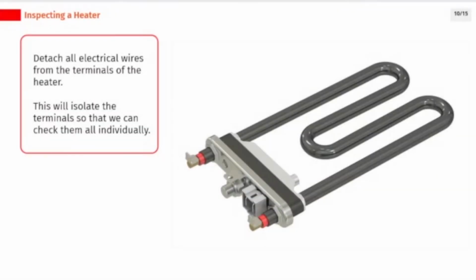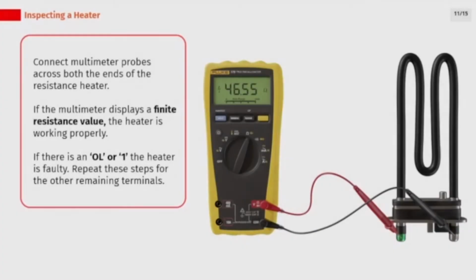Detach all electrical wires from the terminals of the heater. This will isolate the terminals so that we can check them all individually. Connect multimeter probes across both the ends of the resistance heater. If the multimeter displays a finite resistance value, the heater is working properly. If there is an OL or 1, the heater is faulty. Repeat these steps for the other remaining terminals.